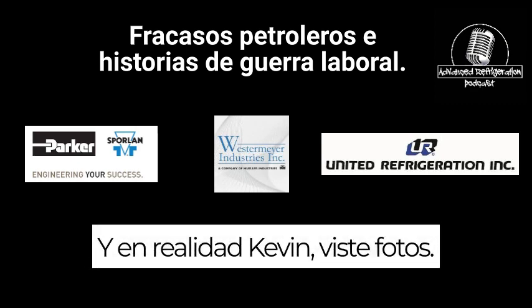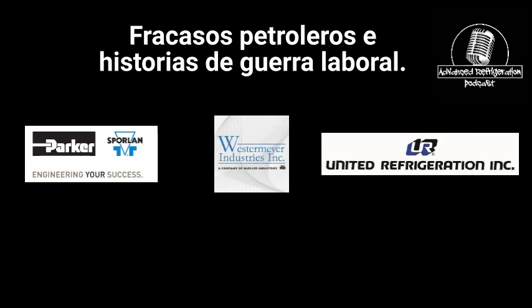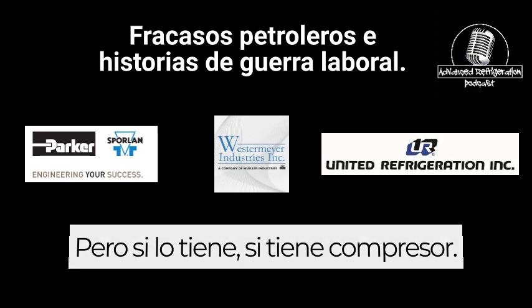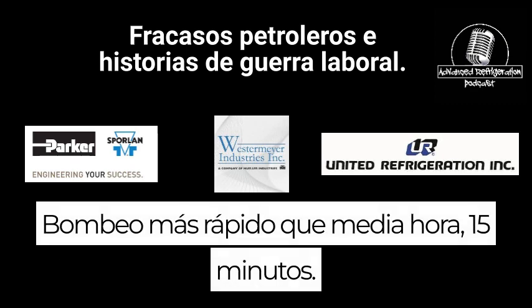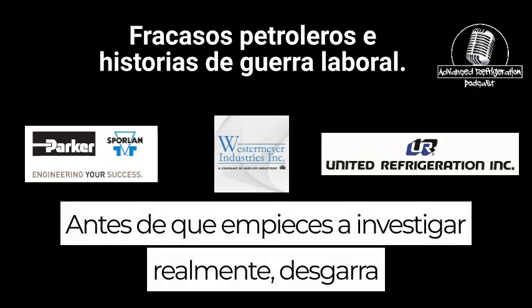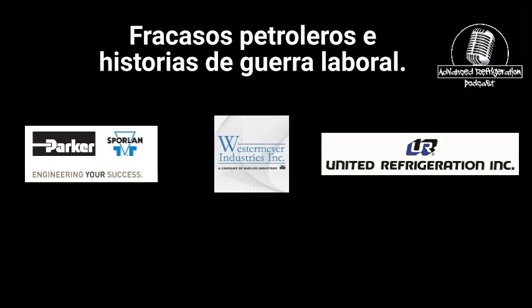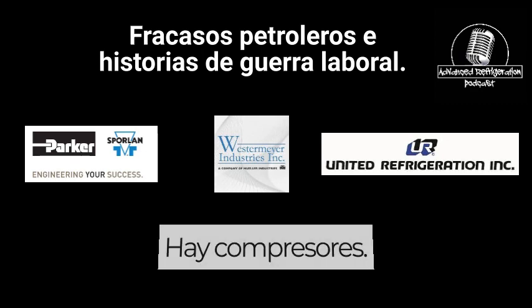And actually, Kevin, you saw pictures. How bad was this one? So that was pretty bad. My compressor pumped out in, like I said, less than 5 minutes. It had to be like 2.5 minutes. But if you have a compressor pumping out faster than an hour, half an hour, 15 minutes, what's your cutoff before you start really investigating and tearing into that compressor? Probably half an hour. Scrolls seem to pump out a lot faster. Yeah, there are some that are 15 minutes.